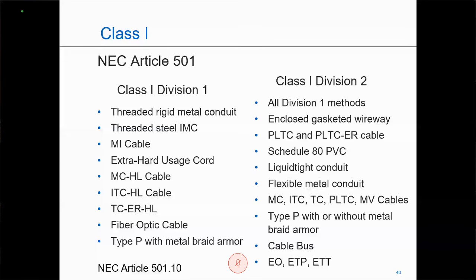But then in 1996, we started seeing some influence from the IEC world on our National Electrical Code, because the IEC world does a lot of open cabling, where here in the United States, we tend to have a lot of conduit systems. So in 1996, the National Electrical Code said if you have a jacketed MC cable and it's tested and listed for Class 1, Division 1, uses a cable gland that's also tested and listed for Class 1, Division 1 in an area with limited public access, this product was now a new wiring method.